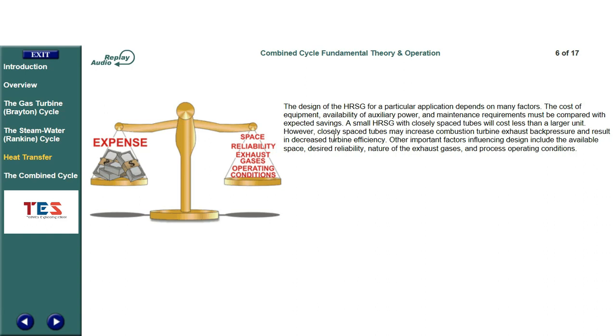However, closely spaced tubes may increase combustion turbine exhaust back pressure and result in decreased turbine efficiency. Other important factors influencing design include the available space, desired reliability, nature of the exhaust gases, and process operating conditions.